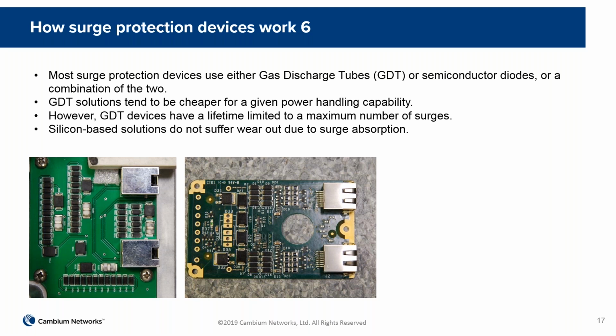And the energy, or the capability of the device, is measured in kilowatts, basically. We can think that the surge only lasts for perhaps a millisecond, but maybe we have 200 volts across it, and we have 100 amps traveling through it. And so you could end up with 20 kilowatts of energy to dissipate somehow. And so the devices would have a 15 or a 20 kilowatt rating, but because they only dissipate it for a millisecond or so, the actual energy dissipated is much lower than the kilowatt rating would imply.